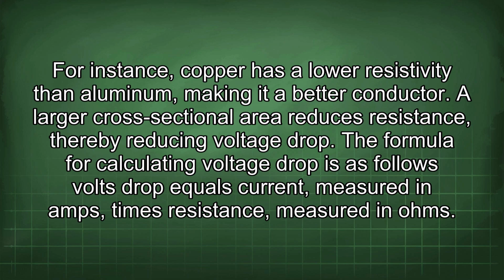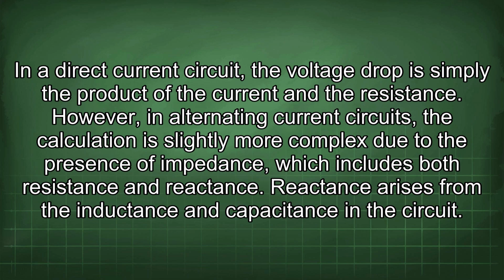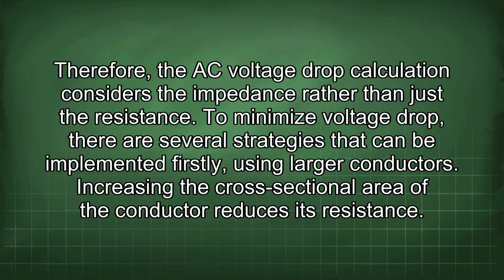The formula for calculating voltage drop is as follows: volts drop equals current, measured in amps, times resistance, measured in ohms. In a direct current circuit, the voltage drop is simply the product of the current and the resistance. However, in alternating current circuits, the calculation is slightly more complex due to the presence of impedance, which includes both resistance and reactance. Reactance arises from the inductance and capacitance in the circuit. Therefore, the AC voltage drop calculation considers the impedance rather than just the resistance.